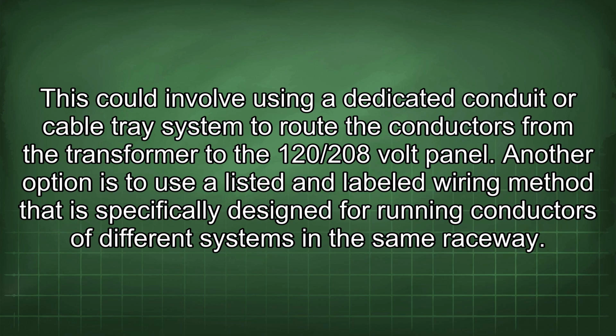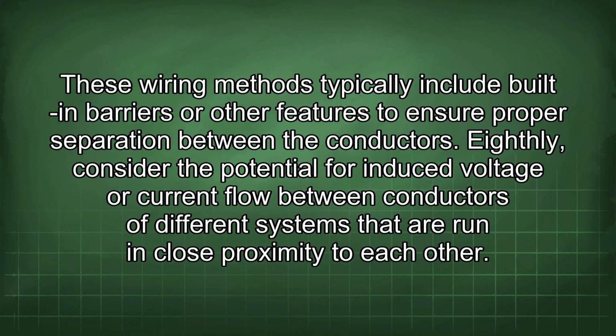Another option is to use a listed and labeled wiring method that is specifically designed for running conductors of different systems in the same raceway. These wiring methods typically include built-in barriers or other features to ensure proper separation between the conductors.